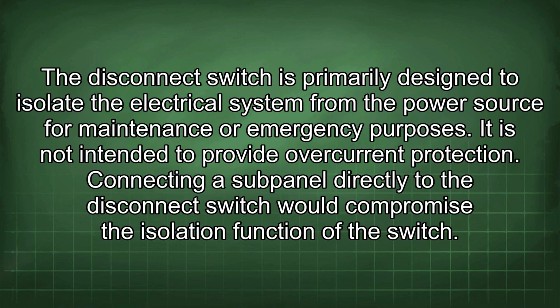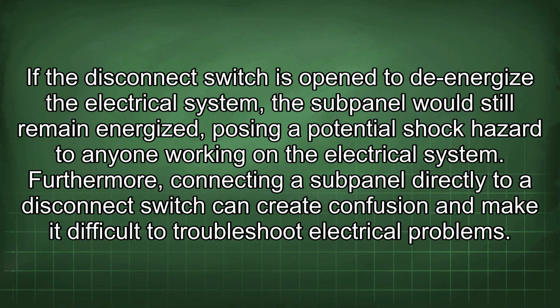The disconnect switch is primarily designed to isolate the electrical system from the power source for maintenance or emergency purposes. It is not intended to provide overcurrent protection. Connecting a subpanel directly to the disconnect switch would compromise the isolation function of the switch. If the disconnect switch is opened to de-energize the electrical system, the subpanel would still remain energized, posing a potential shock hazard to anyone working on the electrical system.